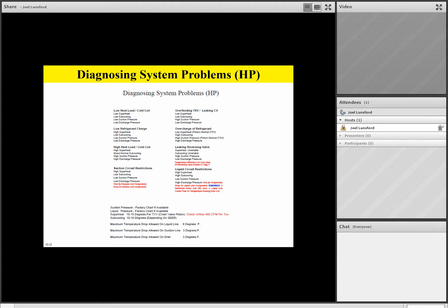Now, at the very bottom of your page, you're going to notice there's some parameters that I'd like you to consider when we're talking about heat pump diagnostics. Number one is if you have a particular factory chart that will give you suction pressure, then by all means use that factory chart. If you have a factory chart available to you on some of our competitors' brands of equipment, and they give you liquid pressure under any given conditions, by all means use that information.